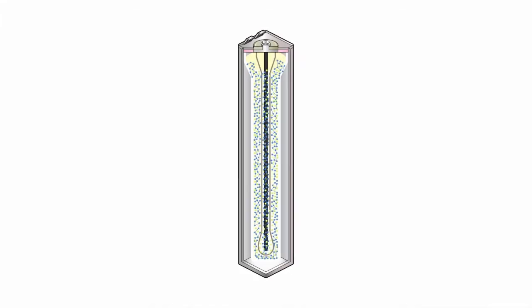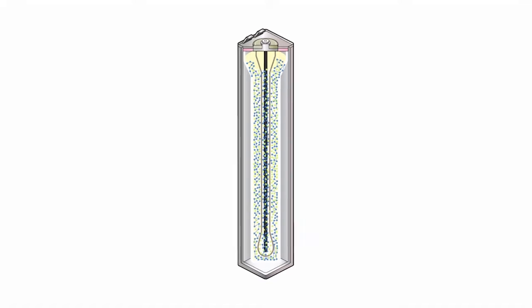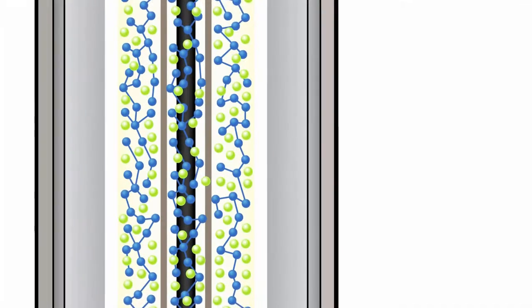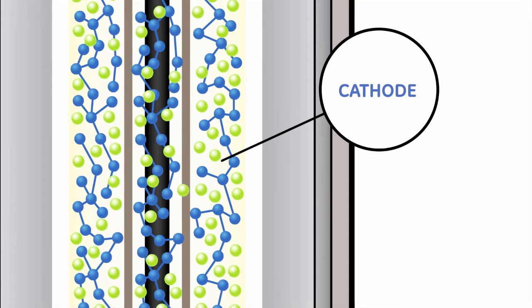The core of the technology is based on a ceramic beta-alumina tube, which is impermeable to liquids and gases. This ceramic tube holds the cathode materials, comprised of sodium chloride salt, nickel, iron, and a salt-based liquid electrolyte.